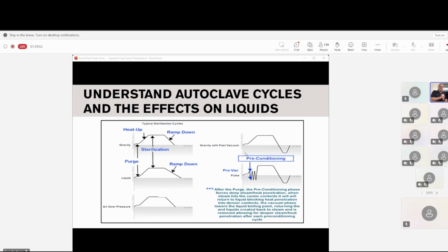But what happens if you have liquids in there? And I've seen people accidentally run the gravity. As soon as you release that pressure, the temperature of that liquid is at 121. I know this happens all the time because I see media all over the inside of the autoclave. And what generally will happen is that valve opens up, and it's a Mount St. Helens eruption. Instantly, we come to an extremely hard boil. You're going to lose about 95% of it. People open the door and go, what happened? Well, you ran the wrong cycle.